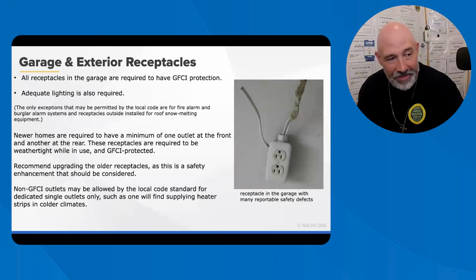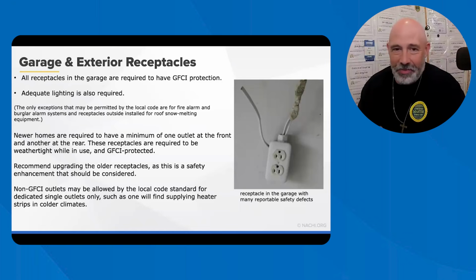Garage and outlets, I've seen this too many times. Make sure that adequate lighting is required. You've got to make sure that every receptacle should be GFCI. Make sure that it's not painted. Make sure that they are mounted properly. If there's any ground or anything like that, make sure you're going around and checking that. Make sure that there's proper wire clamps in place.